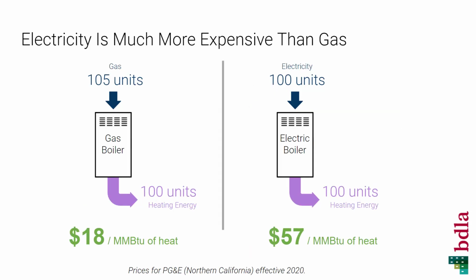The problem here is that electricity on a per unit basis is far more expensive than gas. If you look at the example on the left for a gas boiler, it needs only slightly more gas to produce 100 units of heat, but it only costs $18 per MMBTU, whereas the same system with an electric resistance boiler would cost $57. So it's really a big price jump, and that's often why this technology isn't really applied, especially in markets like California with expensive electricity.